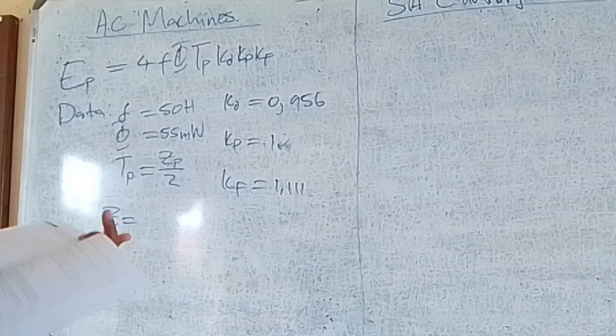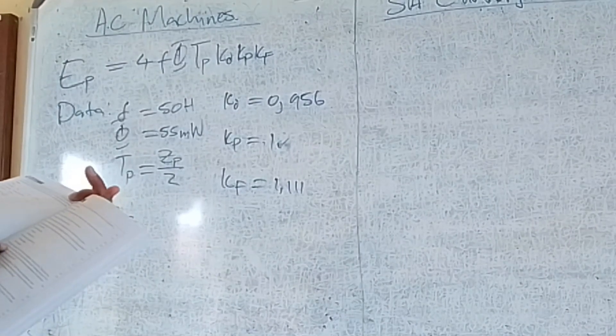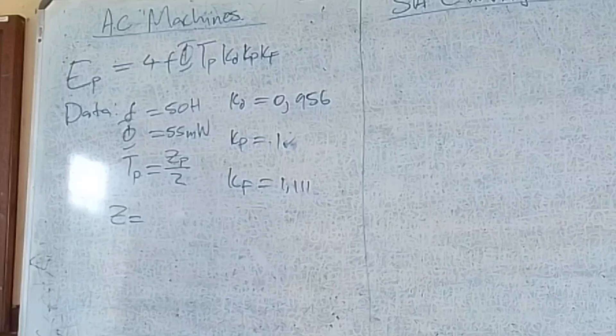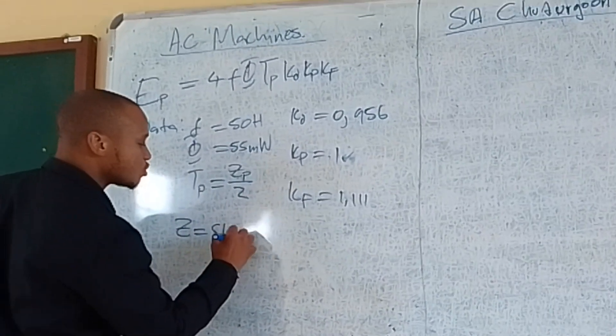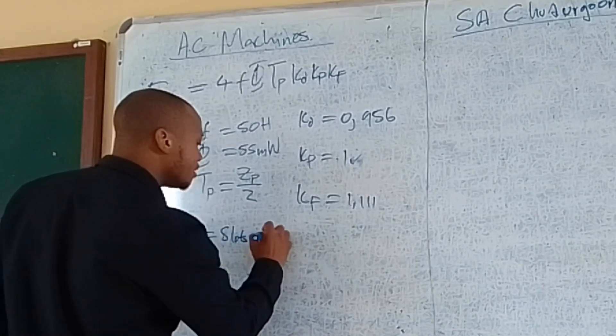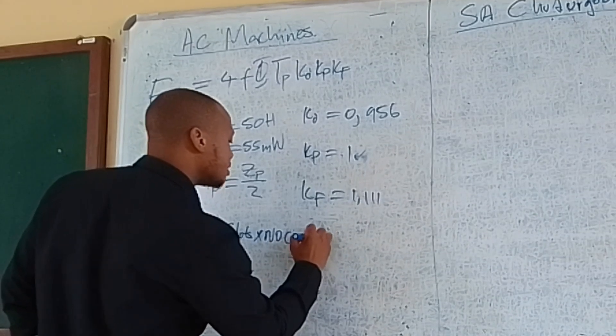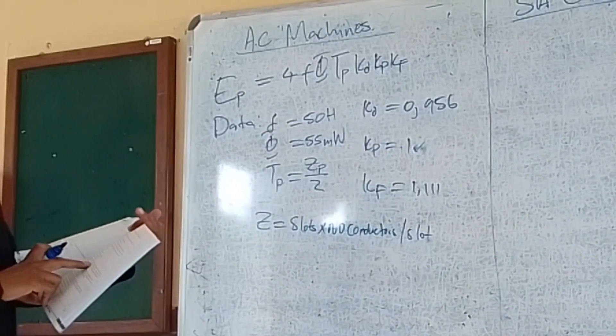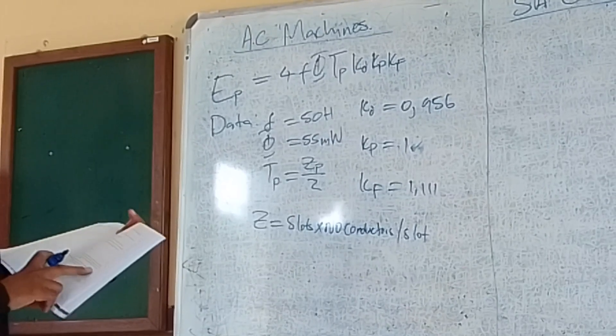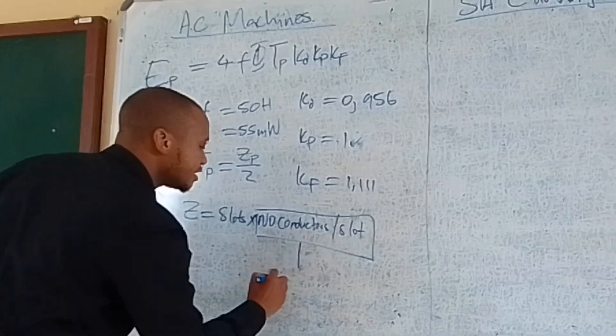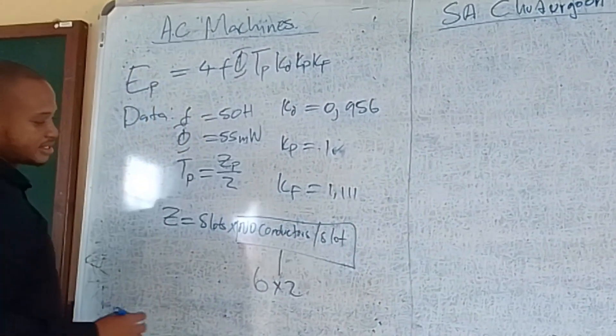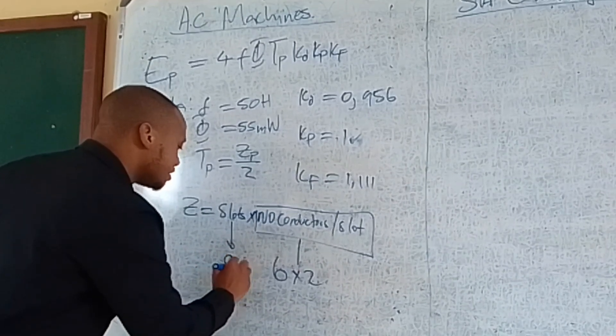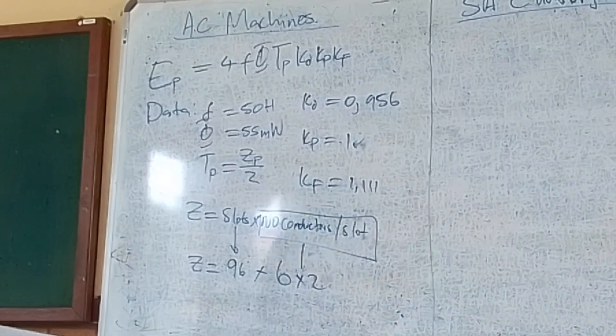The statement says the stator has a total of 96 slots, and it is a 6-turn coil which is fully pitched and double layer. Z is the product of the number of slots multiplied by the number of conductors per slot. This term is equal to 6 multiplied by 2 for the double layer. The number of slots is 96, so Z equals 96 times 12.